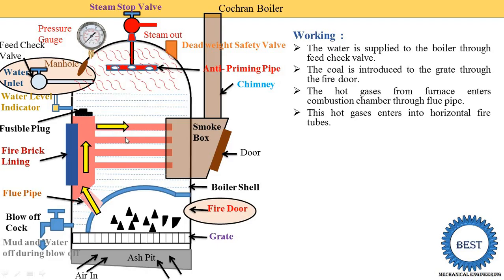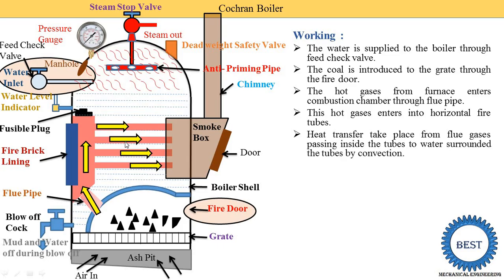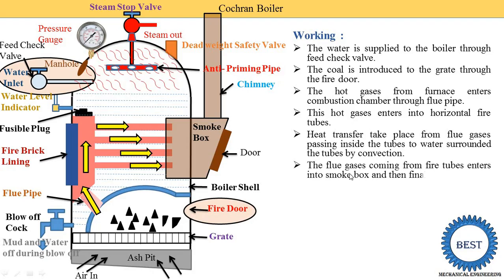The hot gases pass through the different fire tubes, and heat transfer takes place from the flue gases to the water surrounding the tubes. The flue gases heat the fire tube, and the fire tube heats the water. Heat transfer takes place from the flue gases inside the tube to the water surrounding the tubes by convection heat transfer. The flue gases coming from the fire tubes then enter the smoke box and are finally discharged to the atmosphere through the chimney.